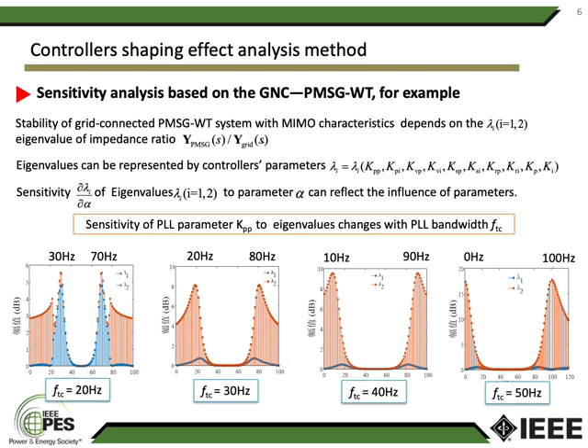According to the previous sensitivity analysis, the corresponding impedance curve can be further derived. As we can see, when the PLL bandwidth changes, the position of resonant peaks in the impedance curve changes as well, and is fixed at F1 minus FTC and F1 plus FTC, where FTC is the PLL bandwidth. Therefore, the influencing bandwidth of PLL can be determined from F1 minus FTC to F1 plus FTC.